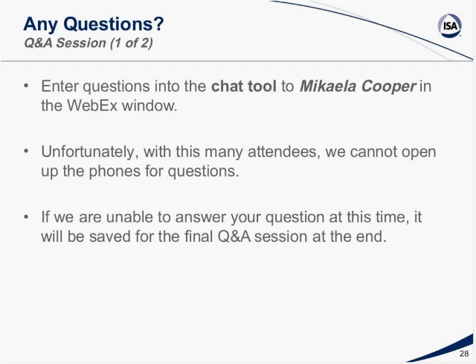Okay, next question. To your experience, what is the minimum and maximum SILs with a manned onshore BMS? Well, as I pointed out earlier, safety integrity levels will be addressed more by Praveen. For most boilers, you consider all the items that are required by the NFPA code to be safety integrity level 2. That's kind of my rule of thumb that we used at P&G, and I think generally in the industry that's pretty well accepted. I would hope Praveen will address that a little bit as he talks about it.